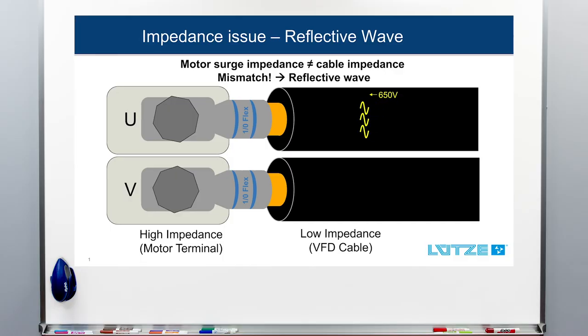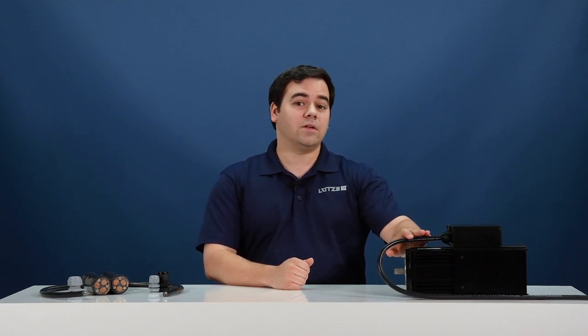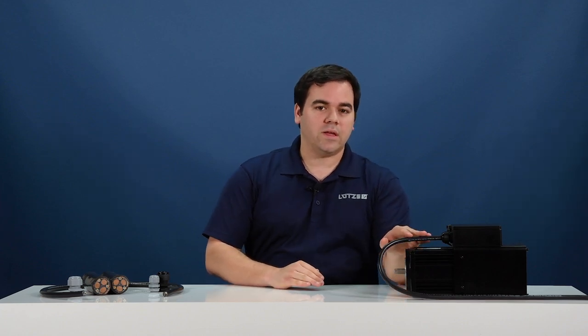Let's go to the whiteboard to discuss this in a little more detail. When an electrical pulse crosses a barrier from a low impedance pathway like a cable to a higher impedance pathway like a motor terminal, the flow is disrupted and some of the waveform is reflected backwards. This reflected wave combines with incoming waveforms to cause high voltage spikes. One way to reduce this effect is to match the impedance value of the cable to the impedance value of the motor so that the energy can flow with less disruption. Because motor terminals have a high impedance value and the cable is intended to be a low impedance pathway, when we bring the cable impedance closer to the motor impedance, less energy is reflected back.